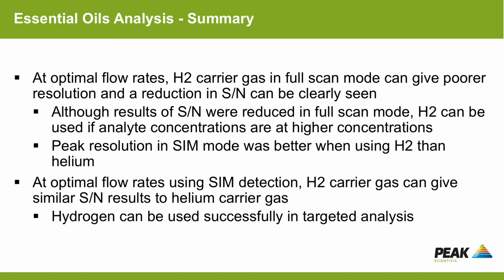And just to reiterate that point on SIM detection, hydrogen carrier gas can give very similar signal to noise results to helium carrier gas in SIM mode. And so for targeted analysis, I would say that hydrogen is definitely a good alternative to helium for GCMS analysis.